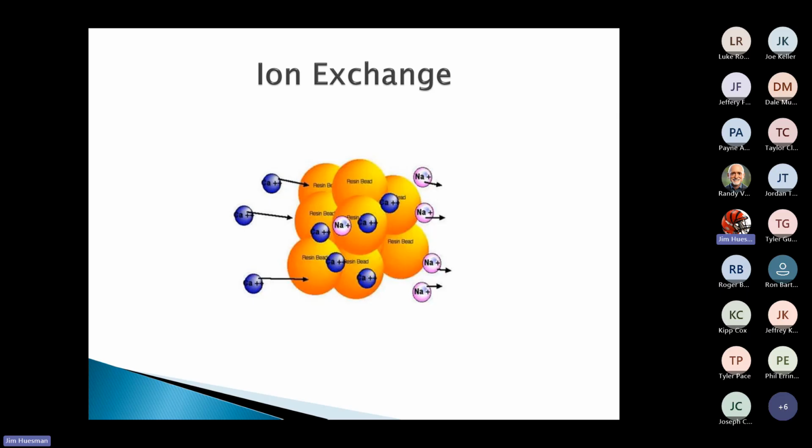But what happens is when the water is entering that tank and it drops down, we have a lot of calcium, which is our Ca+, sodium is the Na, and we'll have calcium and magnesium. What's going to happen is on the exchanges, our calcium is going to come in, hit that media, and stick to it. All right, as soon as it sticks to that base, now what we have is that sodium ion is released.